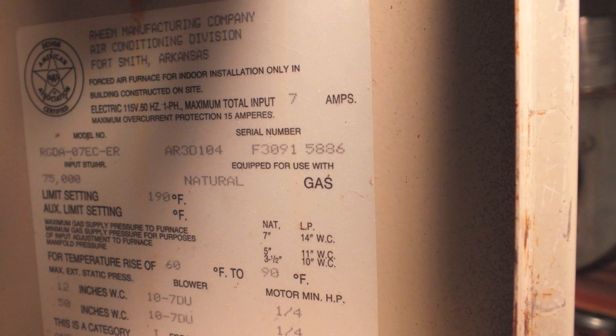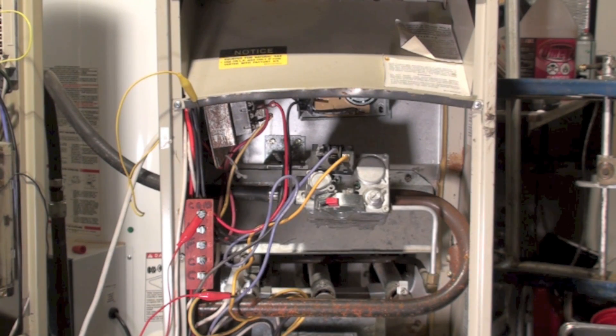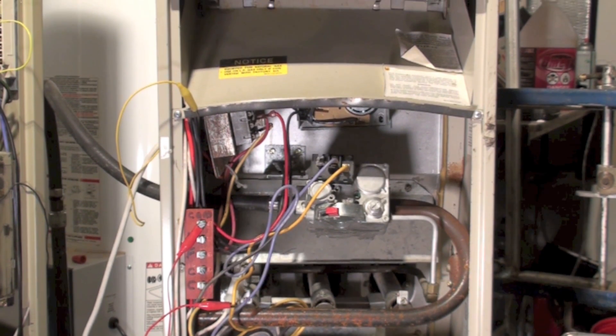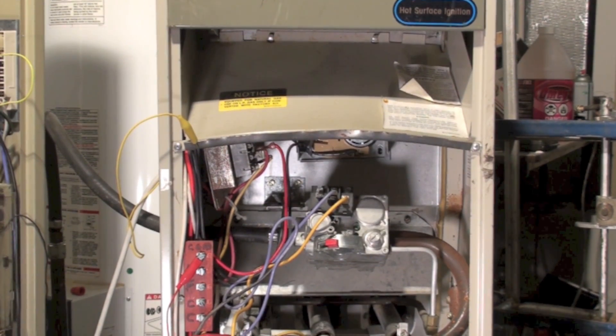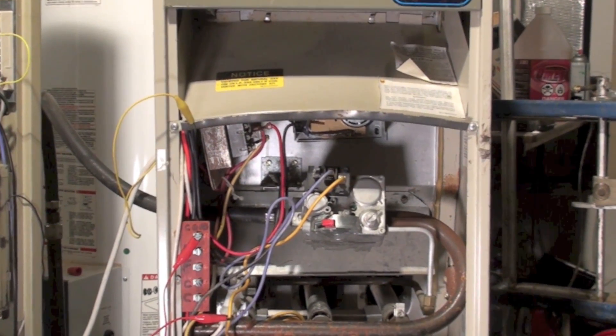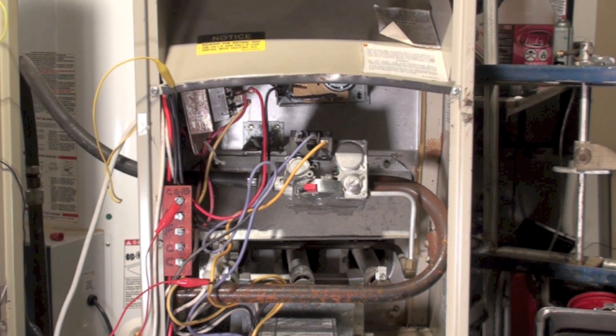This is about the RGDA Rheem gas furnace — one of the kind of odd furnaces. It was made probably around 1986, maybe as late as 1988. It advertises hot surface ignition and was actually a 70% furnace. They put slightly better heat exchangers in these things, still used draft hoods, and did not have inducers, but they did include hot surface ignition.